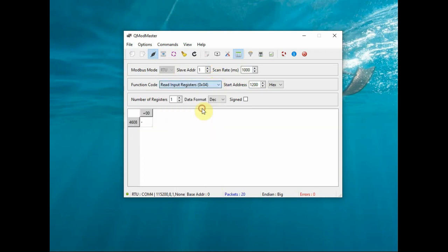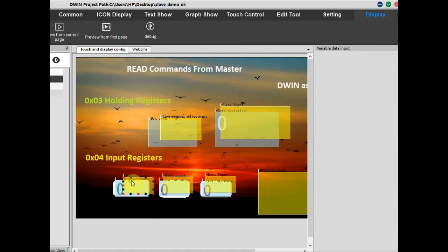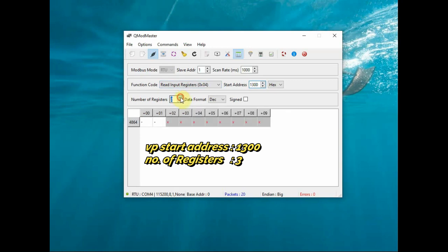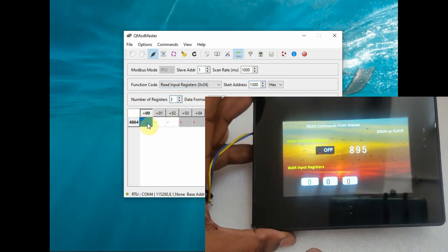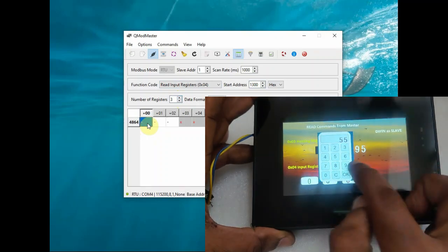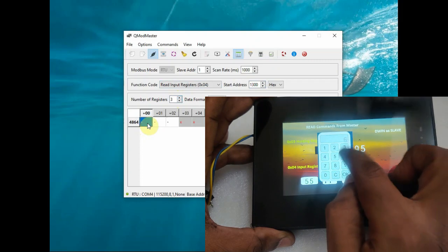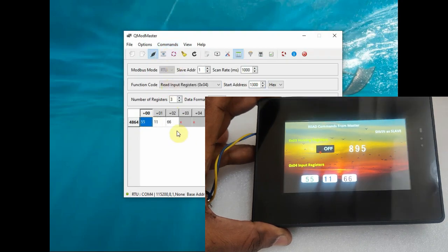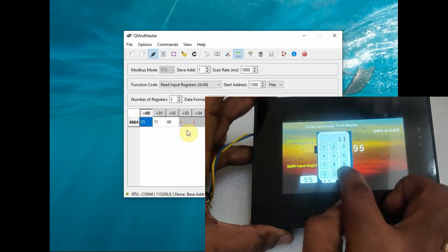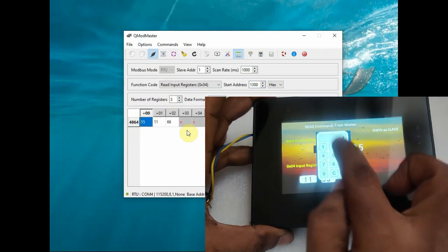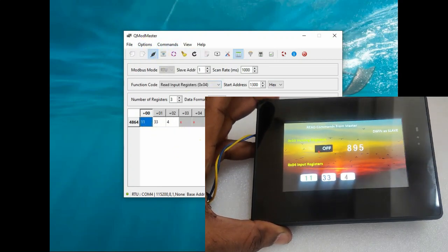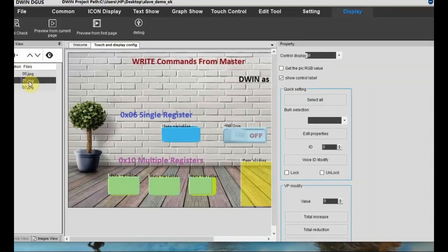For multiple input registers command 0x04, the starting VP address is 1300 with three consecutive VP addresses. Set the start address as 1300 and number of registers as 3. Feed in the values using the pop-up keyboard in the three VP address locations, then click Read/Write to reflect the values in QMod Master. Change the values in the respective VP locations and click Read/Write to see the variation - this is the read input register command.